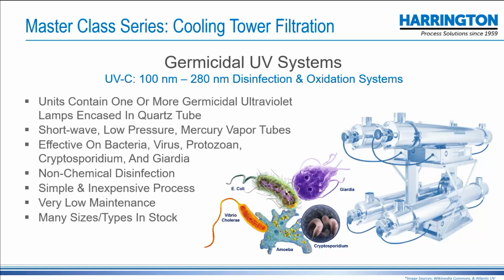But the reality is, if you have a clean tower, if you have a good filtration, you're going to have only trace chemicals you're going to need to feed. And that is going to, for all intents and purposes, also sanitize your tower and eliminate bacterial concern.